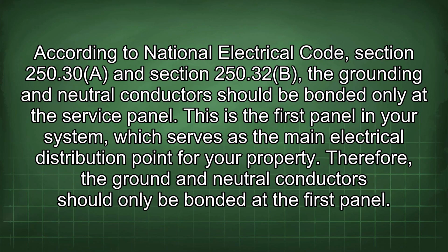According to National Electrical Code, Section 250.30 and Section 250.32(B), the grounding and neutral conductors should be bonded only at the service panel. This is the first panel in your system, which serves as the main electrical distribution point for your property. Therefore, the ground and neutral conductors should only be bonded at the first panel.